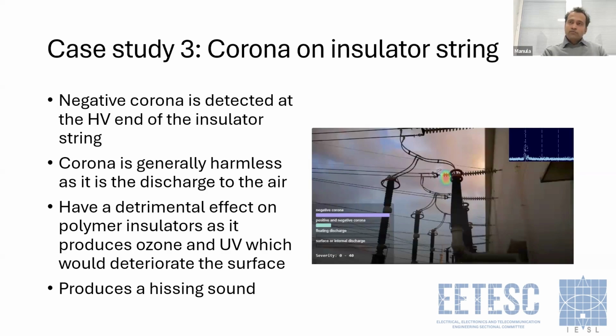But there are types of insulators, for example polymer insulators, that might deteriorate or suffer a detrimental effect from this corona discharge because of the production of ozone and UV that would erode the surface of the polymer insulator. So there are that kind of cases, but in general corona discharges are harmless unless you are worried about the hissing sound and radio frequency interference and these kinds of things. Usually corona is harmless and no action would be needed.